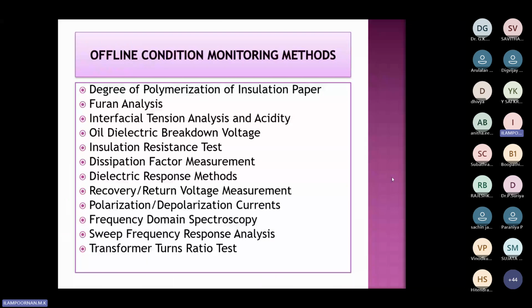So a brief overview of two kinds of methods: one is the offline condition monitoring method, and another one is online. In the offline condition monitoring method, we are going to discuss the degree of polymerization, furan analysis, interfacial tension analysis, and acidity of oil, then dielectric breakdown of oil, and insulation resistance test.